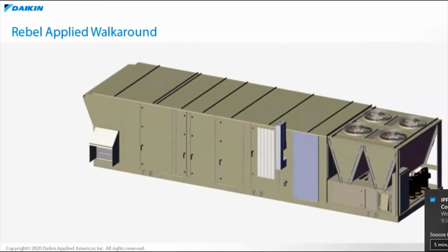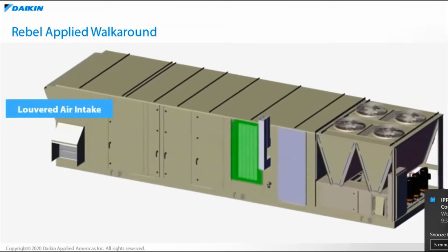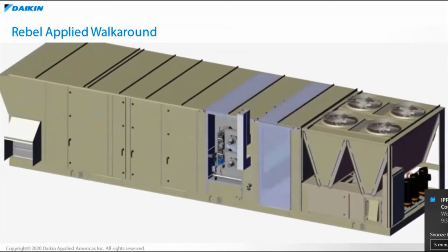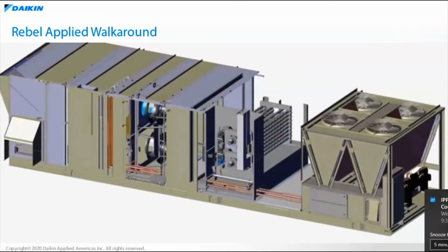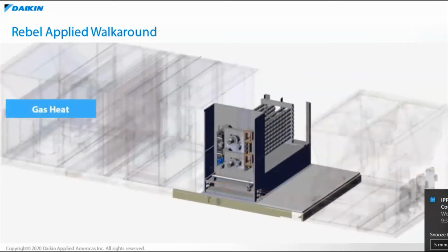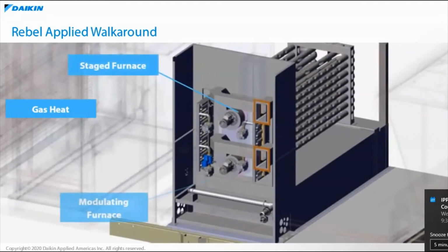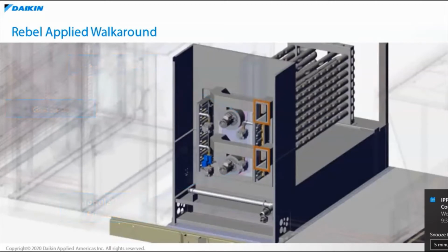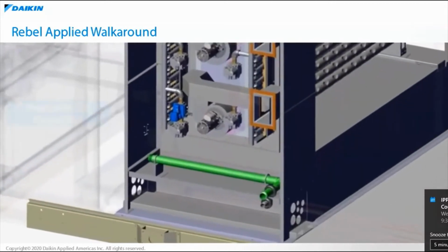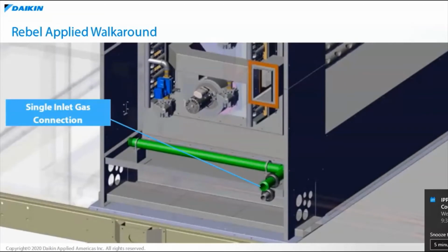The Rebel Applied's heat section is after the supply fan section and houses optional gas or electric furnaces or optional hot water or steam coils. With a gas furnace, the access door will have a louvered air intake. This example shows a staged and modulating gas furnace. The staged furnace is on top and the modulating furnace is on the bottom, with vertically arranged in-shot tubular heat exchangers on either side.